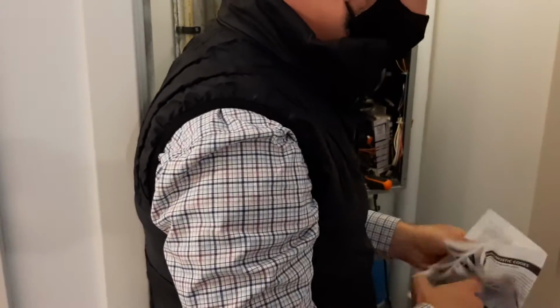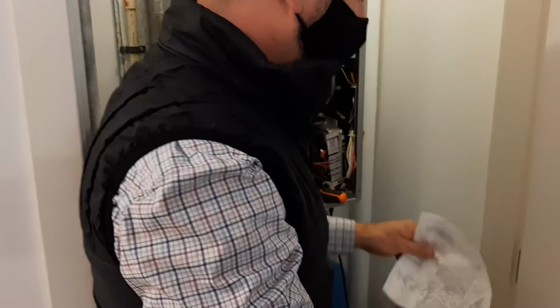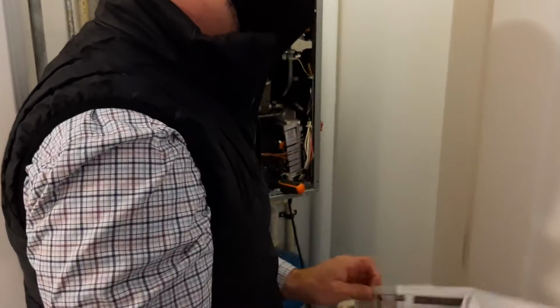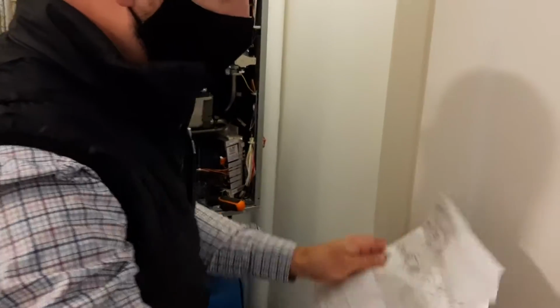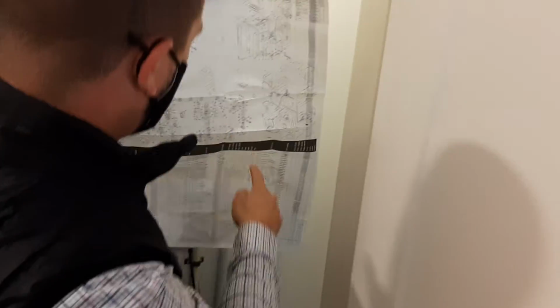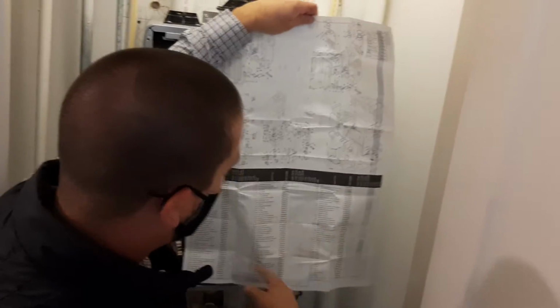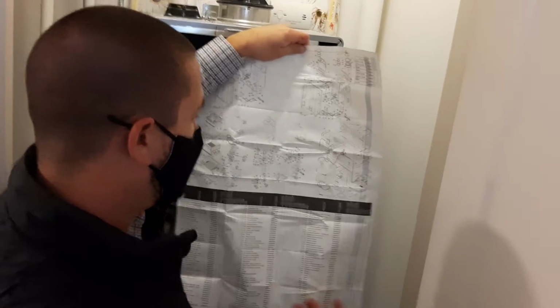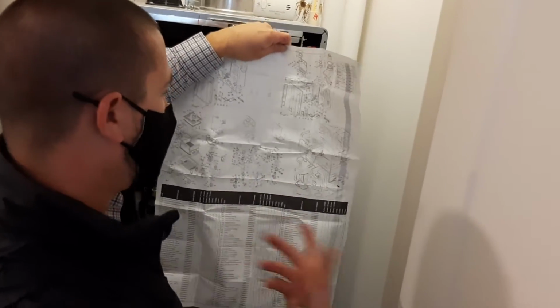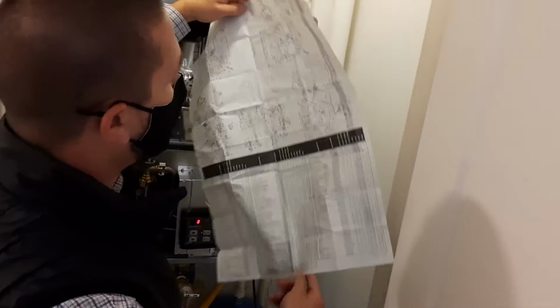Right here in the back is a wiring diagram, but this is the most important piece: the tech data sheet. It's on every unit, or it should be, unless someone has already removed it. It unfolds like a tent, tough to get back inside the case, and that's because it's got a lot of info on it. It lists every part and piece inside the unit, every screw, every part number. So if you need something later on, this is an easy way to get it without just saying, I have one of those tankless water heaters and I need an igniter.